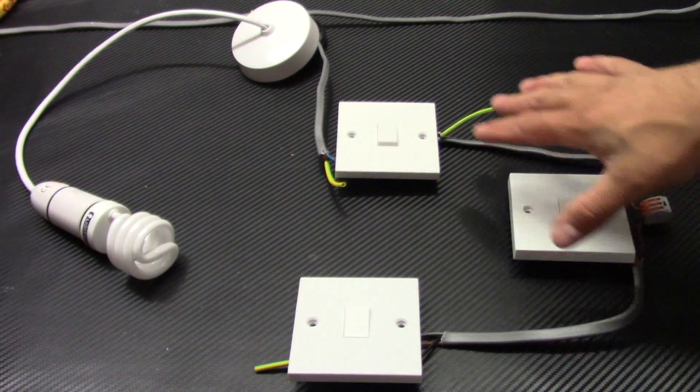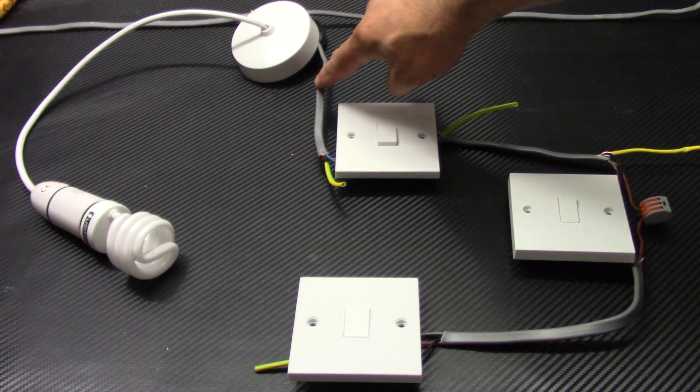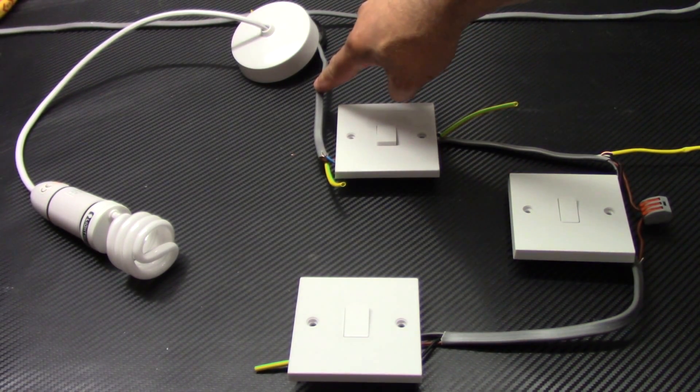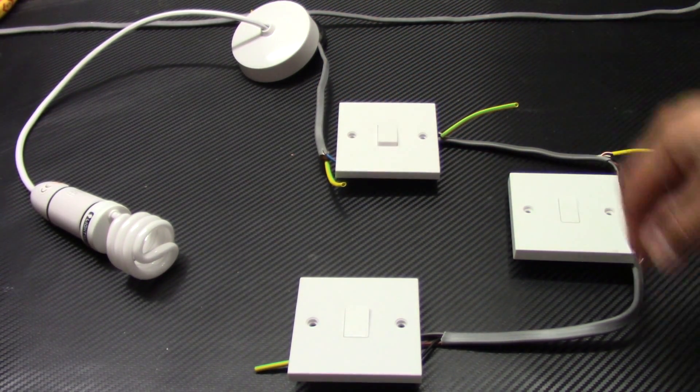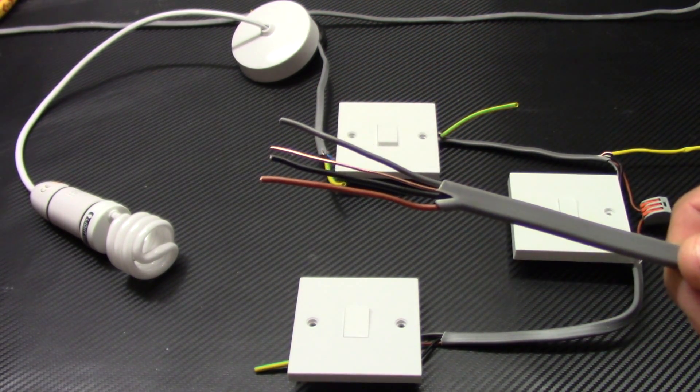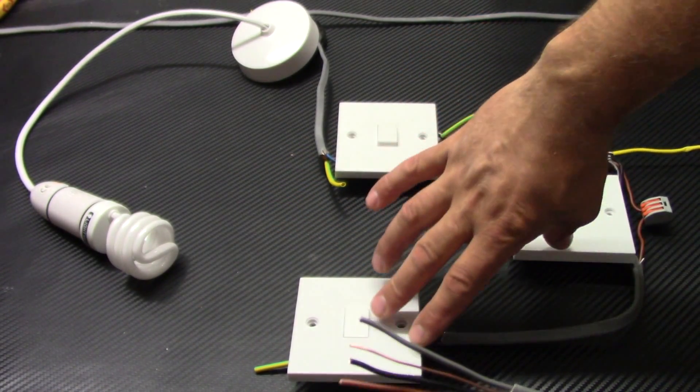To connect all of the switches together what you need? You need twin and earth 1.5 or 1 millimeter from the ceiling rose to the first switch and 1mm 3-core and earth between these two switches and these two switches.